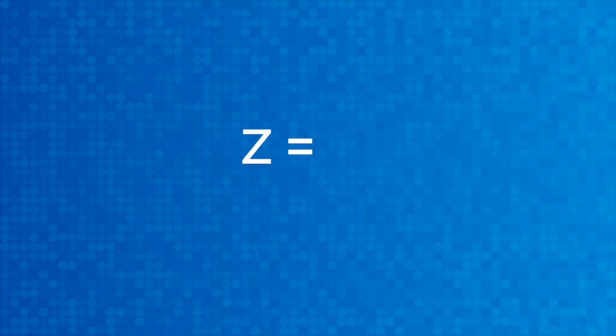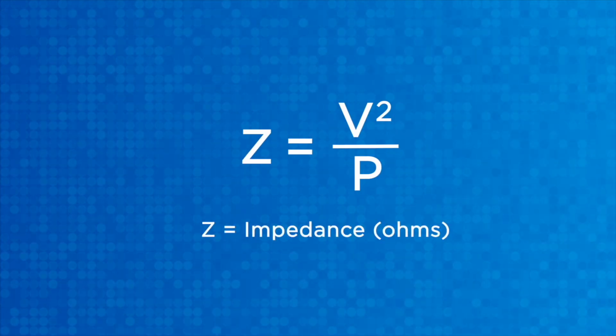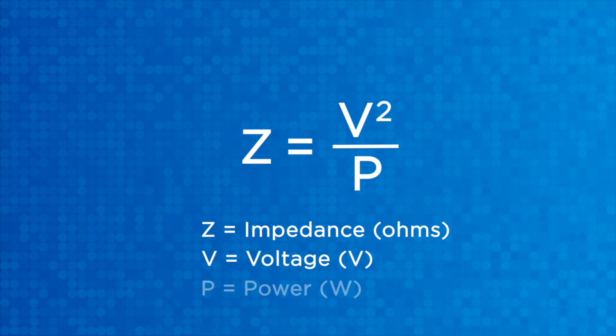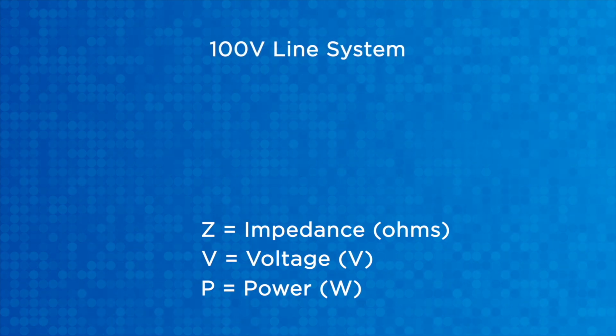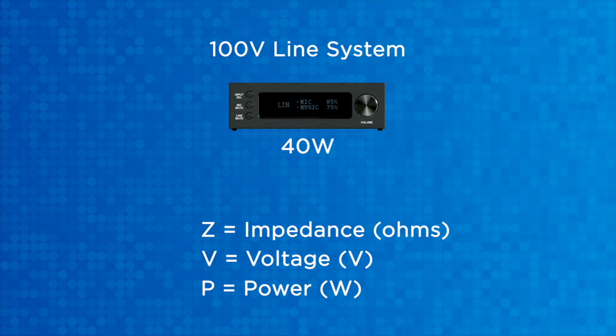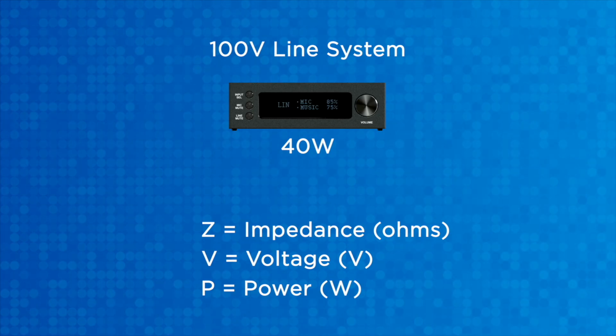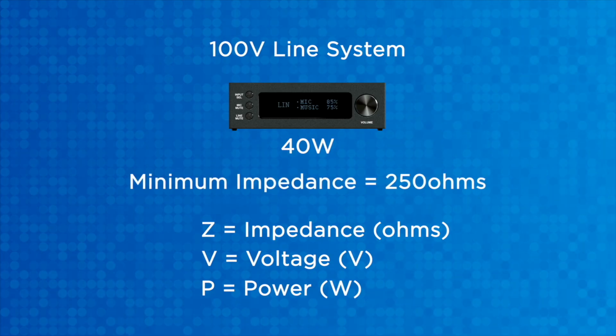When trying to work out the size of the amplifier that is required, or trying to establish the max speaker load that you can safely use on your high-level speaker line system, we'll first need to know certain values or parameters. When you want to find the minimum impedance value that's possible on your given 100 volt line speaker load, the formula is Z equals V squared divided by P. That's impedance equals voltage squared divided by power. For example, if you have a 100 volt line system and a 40 watt amplifier, then you will need to measure the total load of your high level speaker system. In this example, the minimum impedance equals 250 ohms.